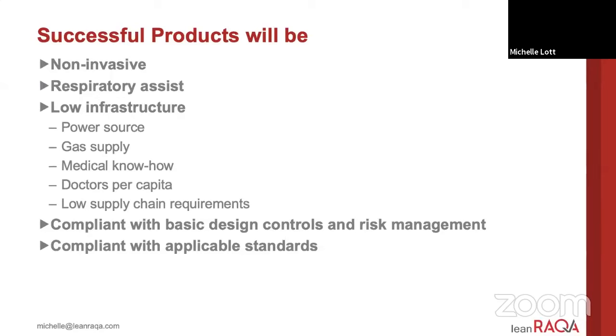So what does that mean for the open source community and what your successful products will be? This is my personal opinion, but I feel like the successful products are going to be non-invasive and respiratory assist in nature. They're going to be low infrastructure in terms of power source requirements, gas supply, and medical know-how. They're going to take into account the doctors per capita in the country where they intend to distribute them. And they're going to be low in supply chain requirements, both to manufacture the device and in the healthcare environment. They are going to be compliant with basic design controls and risk management and compliant with applicable standards.